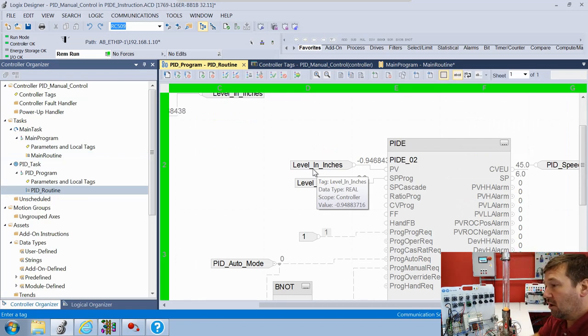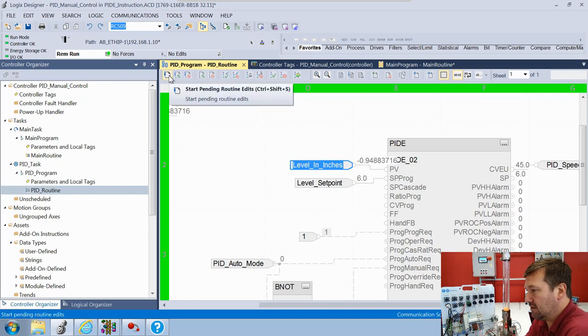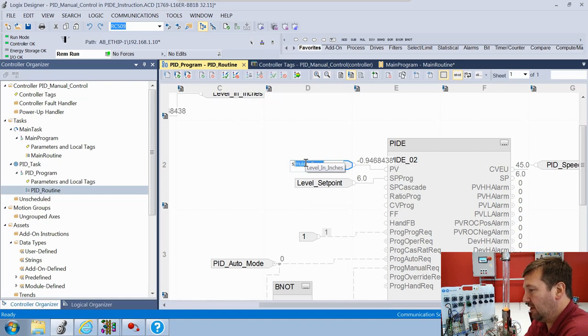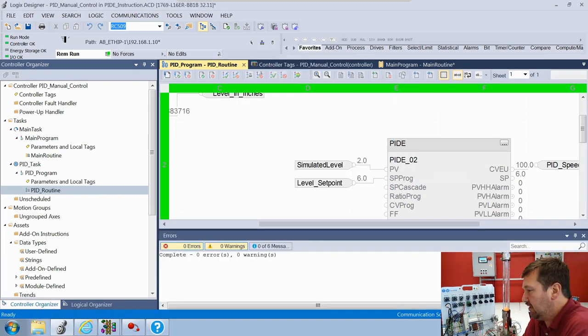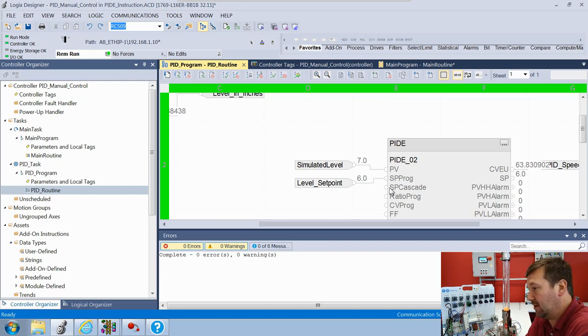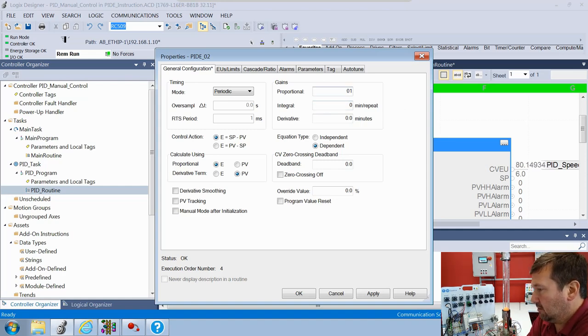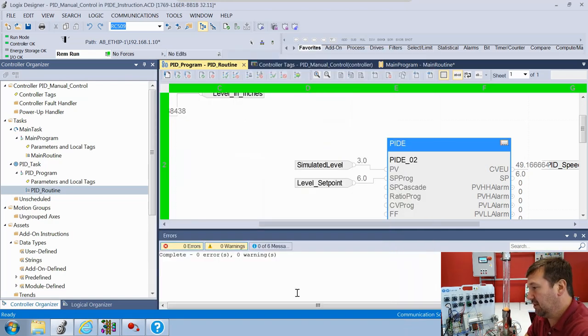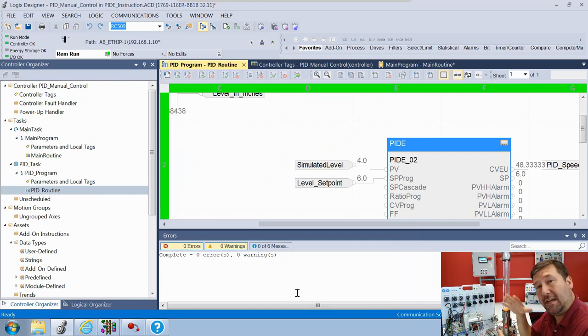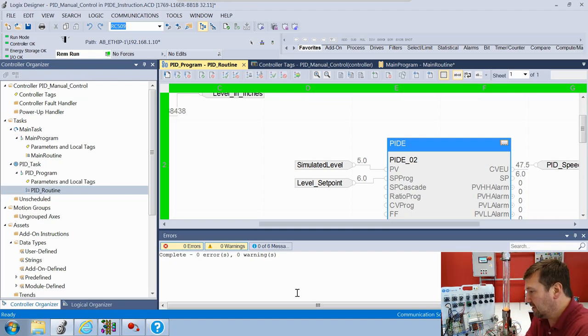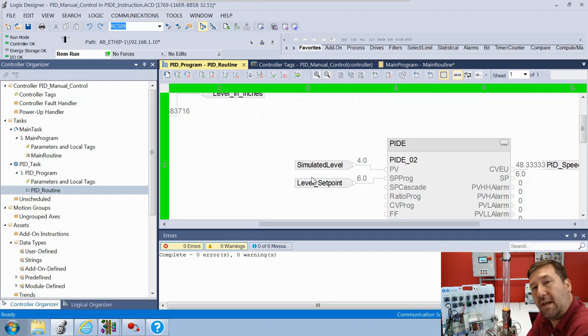Now let's go to our PID routine. Right now our process variable is the actual level coming off the level sensor. We're going to change that to the simulated level - start a pending rung edit and change it to simulated level. Now let's take the integral out of it by setting it to zero, and let's bring our proportional down to 0.1. The main thing is I just want to get it staying within the bounds of zero and 100.